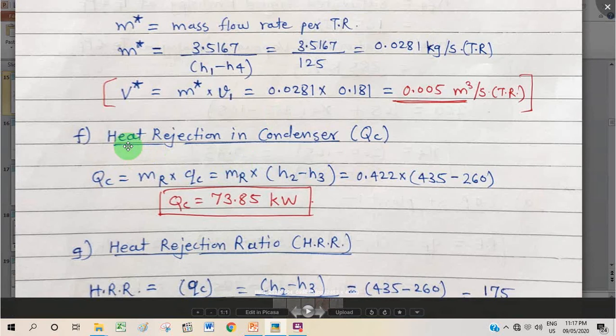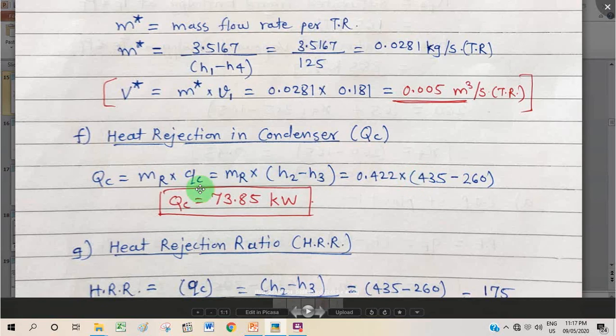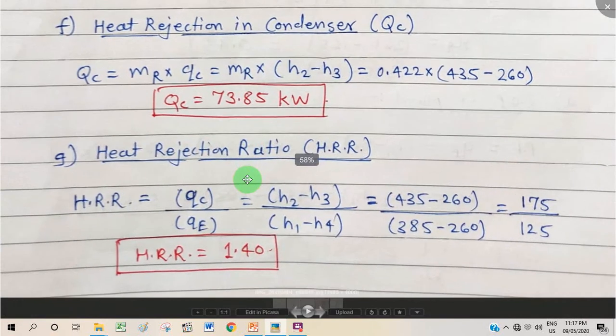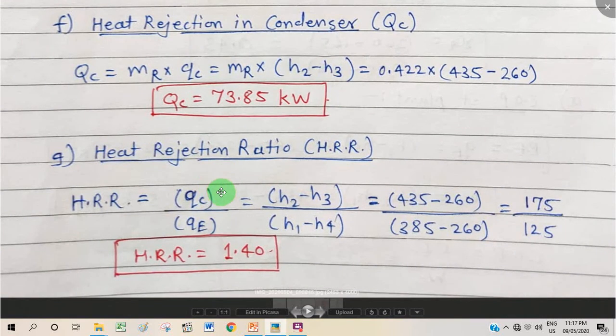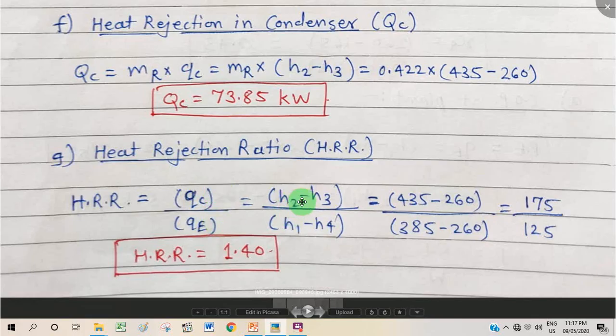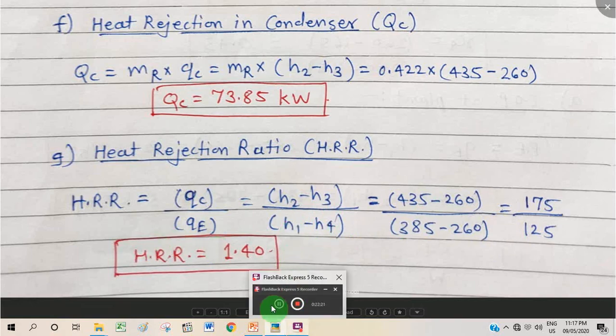Heat rejection in the condenser: Qc = mr × (h2 − h3) = 0.422 × (435 − 260) = 73.85 kW. Heat rejection ratio = (h2 − h3) / (h1 − h4) = 175 / 125 = 1.4. With these results, all required quantities have been found.